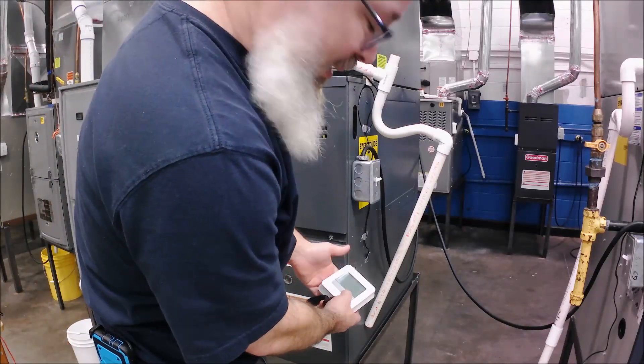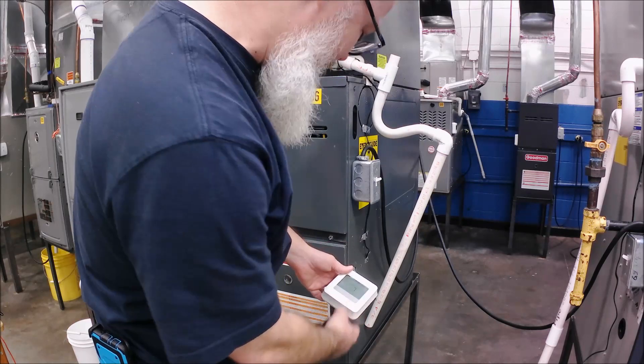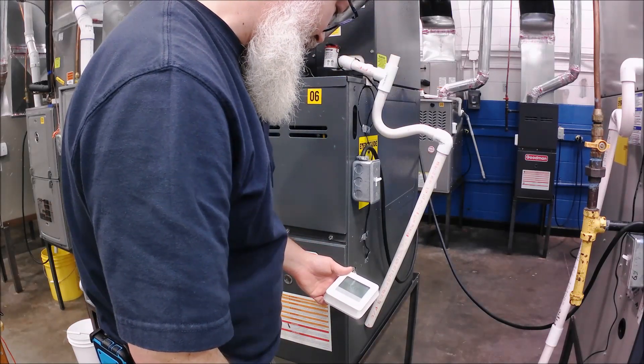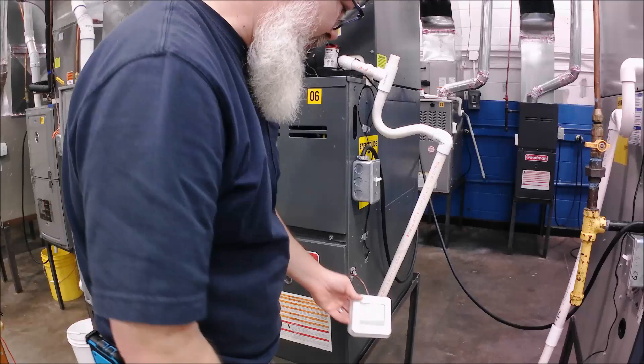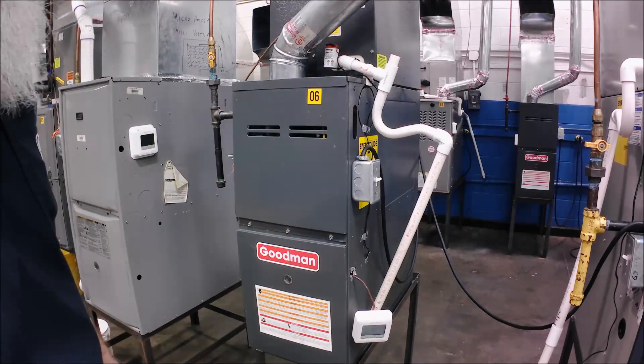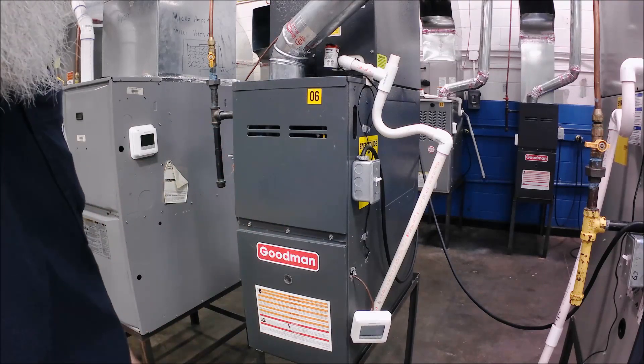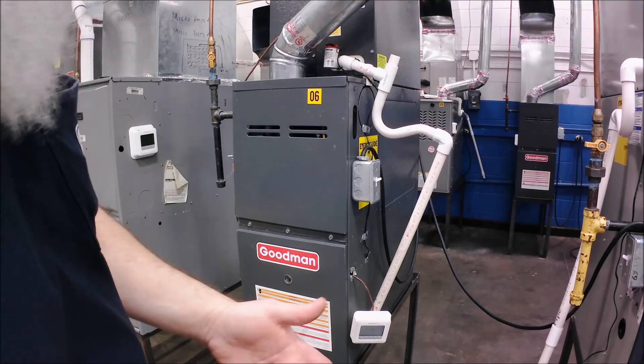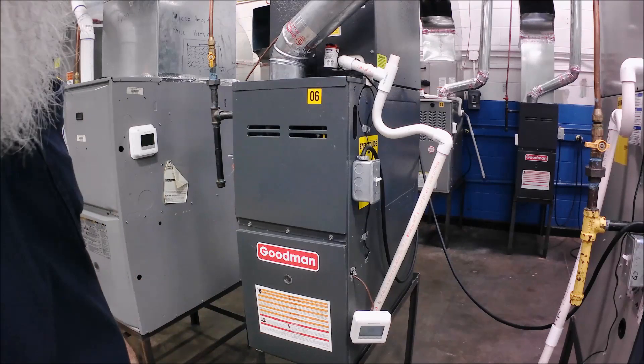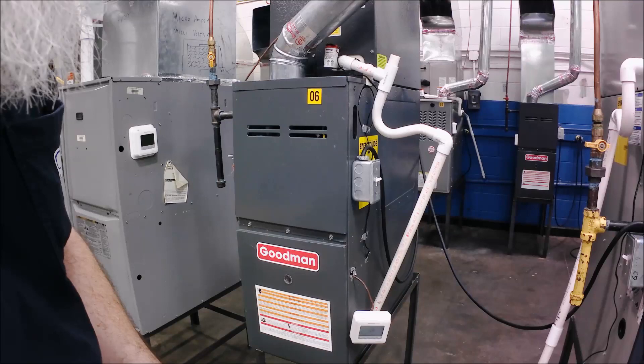I still never fixed the thermostat, but I'll get around to it. My thermostat says heat on, and I can already hear the inducer motor running — so usually that does not happen that quick. We'll let it run for a second, and I'm going to take this cover off and we'll see what it does.